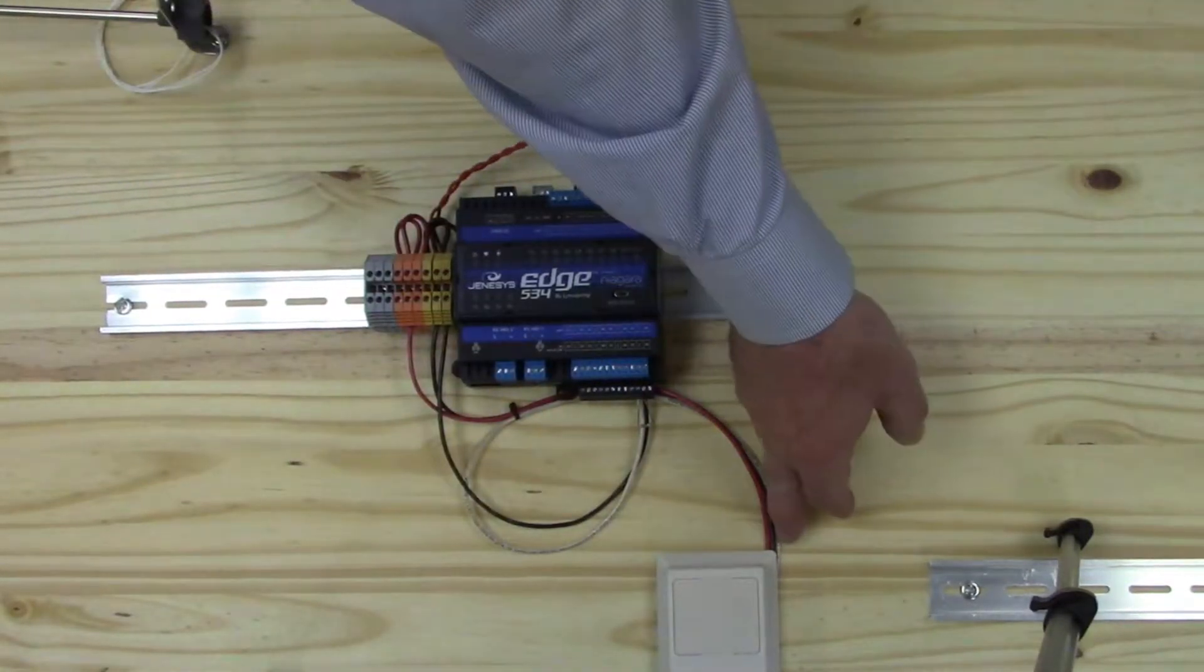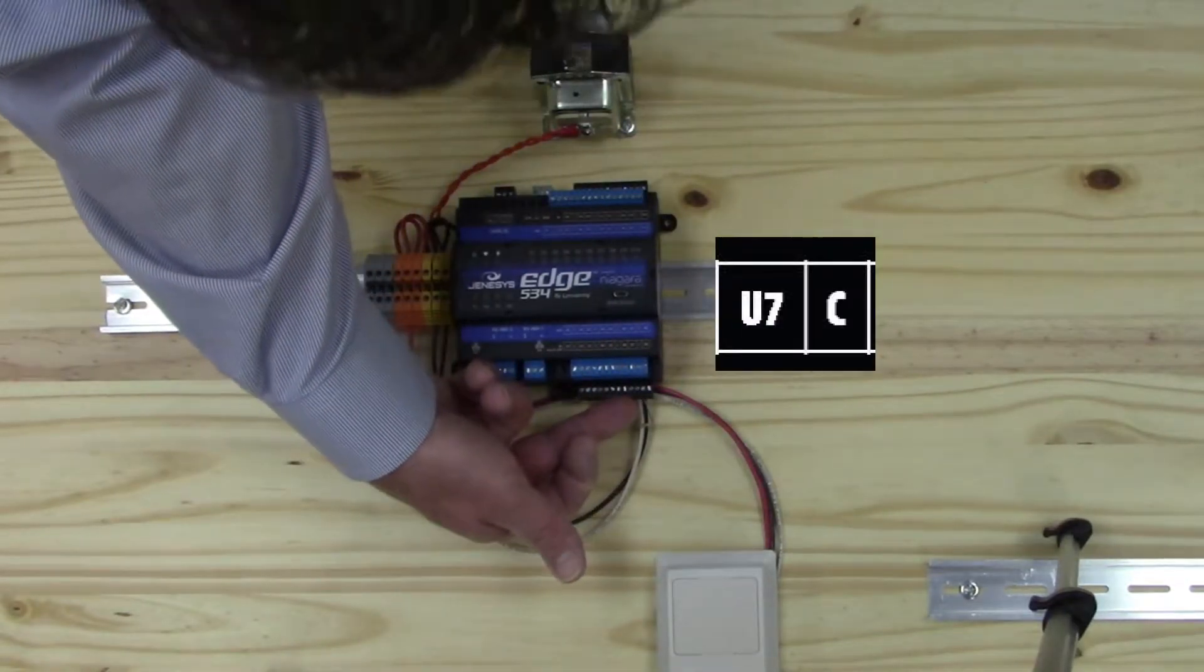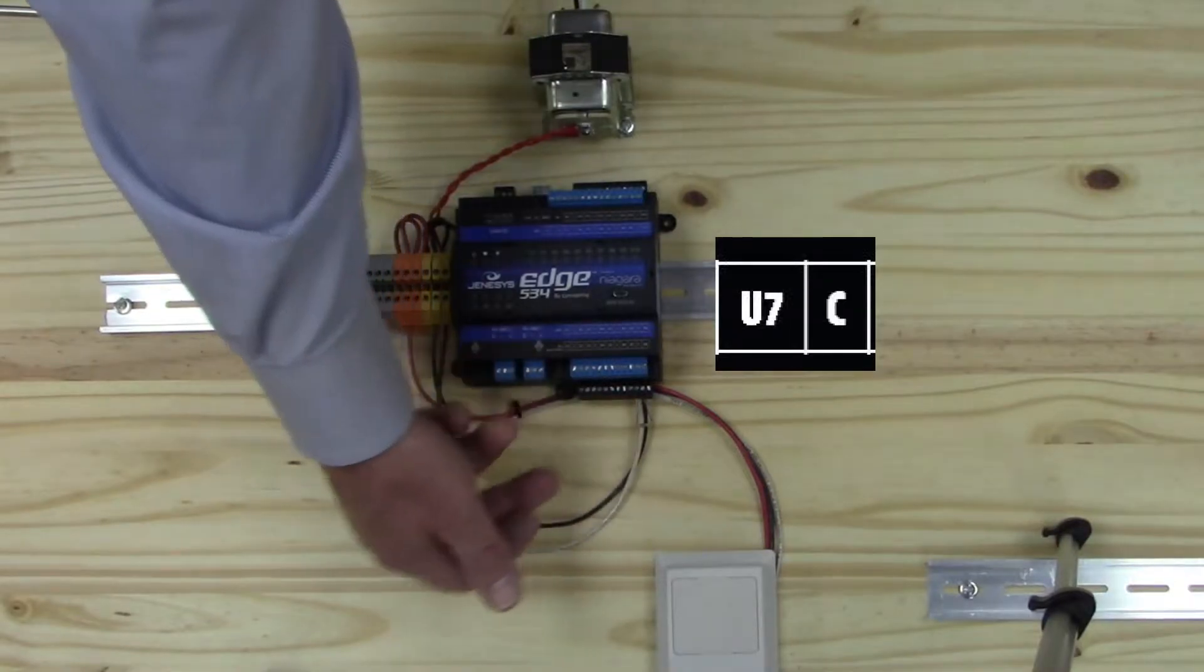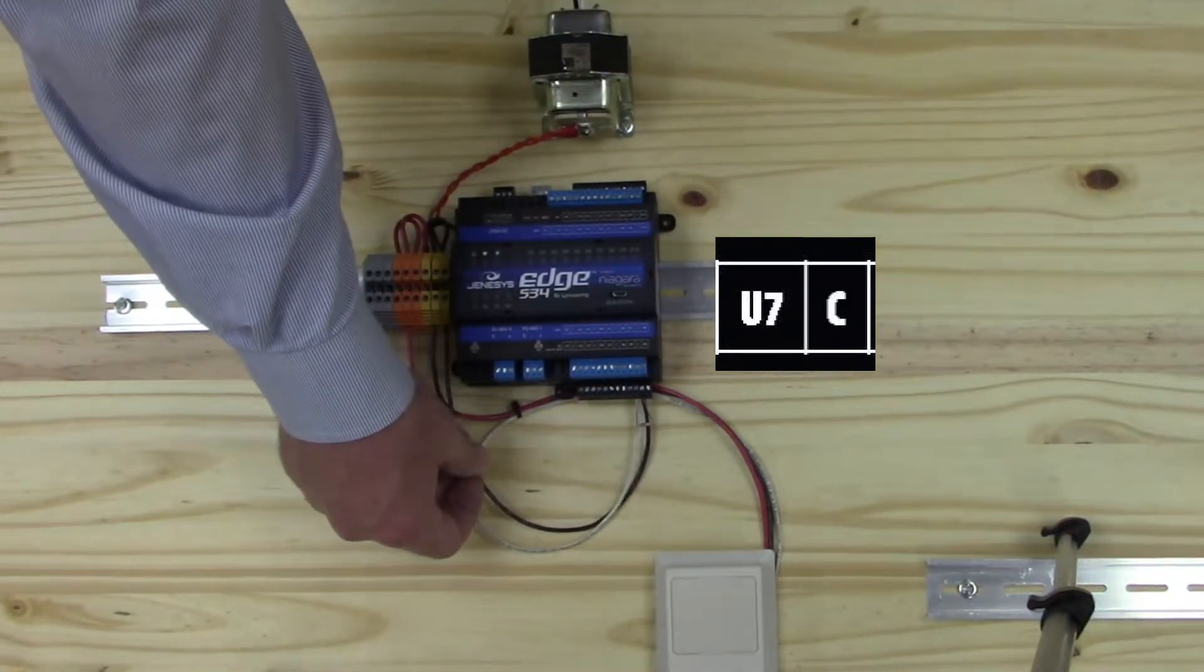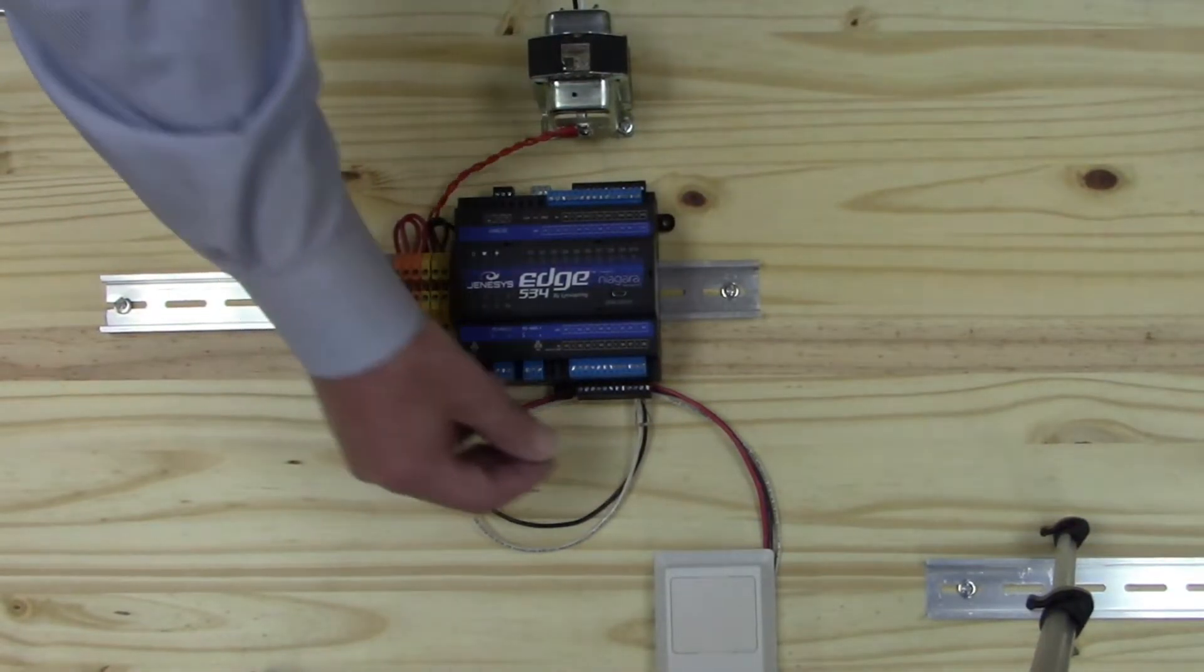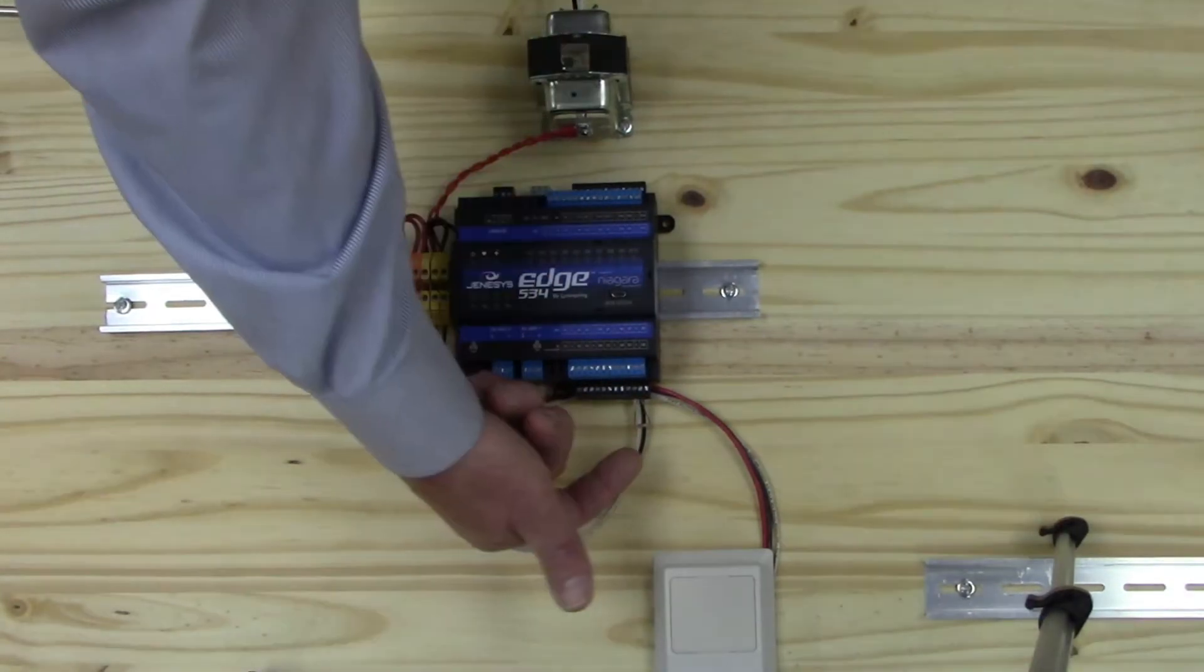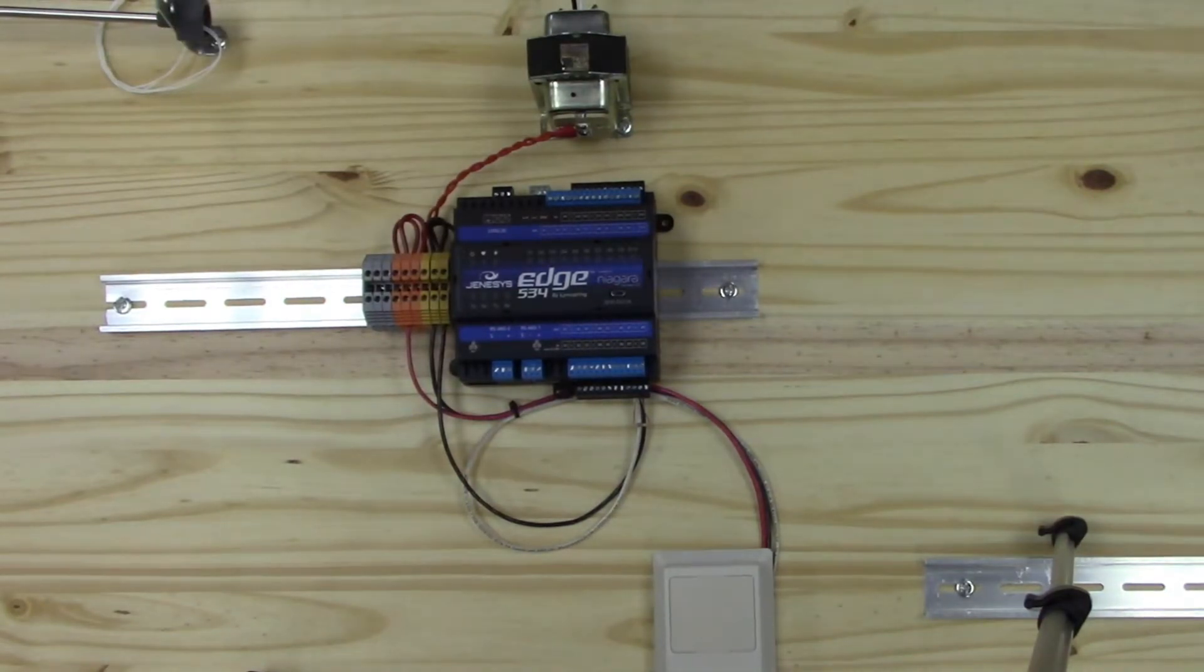The signal from our humidity sensor is this white wire. It is coming in, in this case, U7, universal input 7. And then we connect, complete the circuit by using this black wire back to the common of the transformer. And then finally adding a 499 ohm resistor to complete that signal for us.